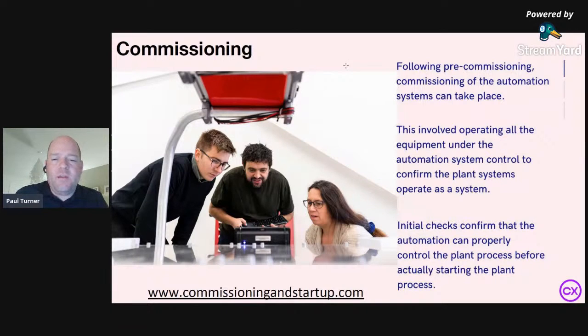What this would mean, for example, is say you've got a level sensor in a tank. When you get to that high level sensor input and that device is triggered, maybe the next logic function is to turn on a pump. You want to see that that pump actually turns on as controlled by your logic. Maybe you then get to the next higher level sensor in the tank, and at that point it kicks in another pump. You want to see that that second pump is going to run.